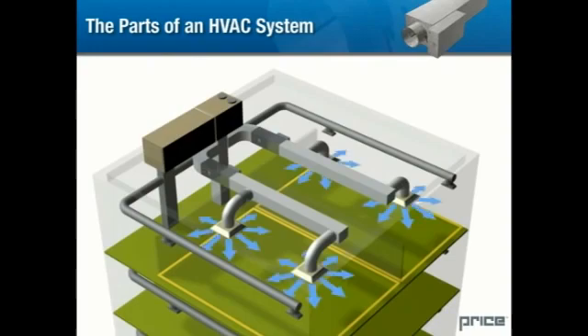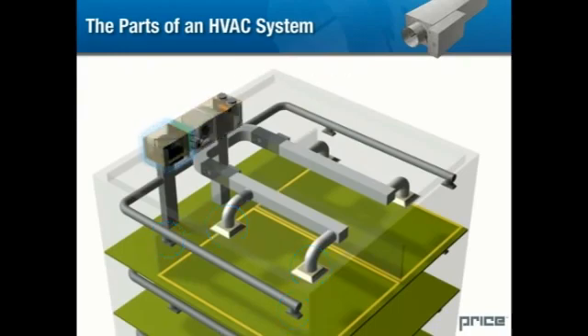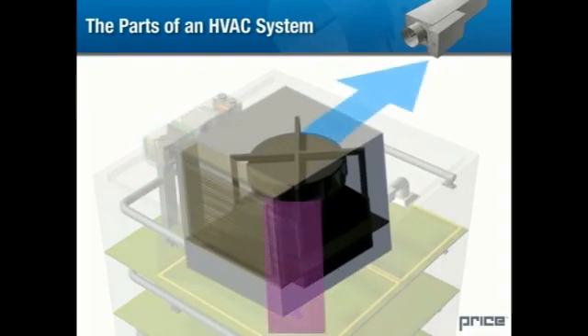Once air enters a space, where does it go? Air circulates through the return inlets and returns to the air handling unit. Unlike an air outlet, a return requires no sophisticated vanes. However, the relative location of the air inlets and outlets can be critical to the efficiency of the system. Upon returning to the air handler, a certain portion of the return air is exhausted and replaced with fresh exterior air — approximately 10 to 20 percent in an average office building or commercial space.